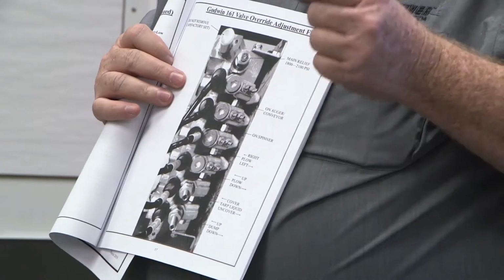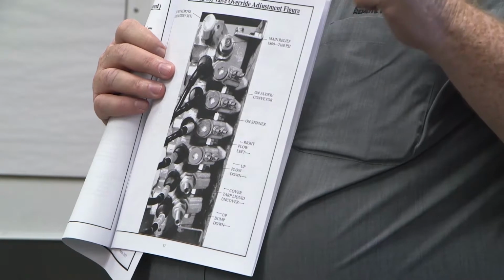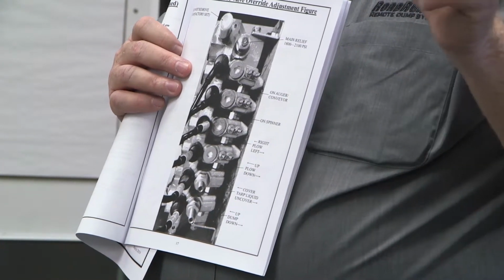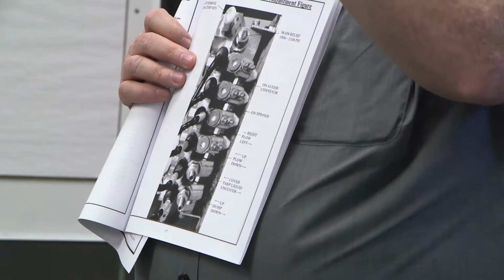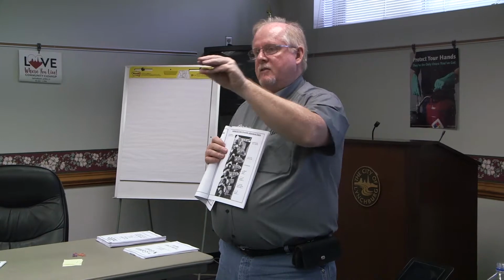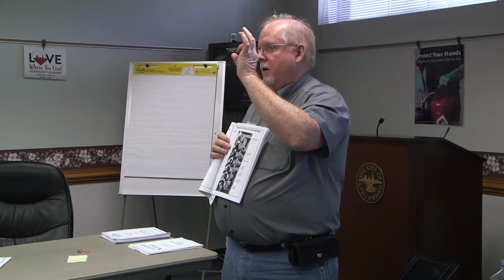What that is actually is a setting that they have to set at the factory because these valves are actually hydraulically shifted. Back in the old days, we used to have a coil this big around. That coil would just manhandle that valve and shift it back and forth because the coil was this big around. Nowadays, we're using a very small coil. I'll show you right here.